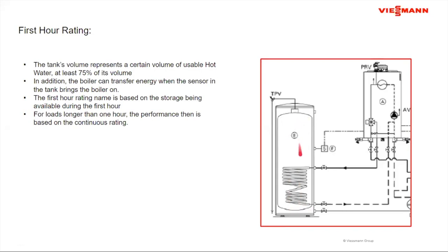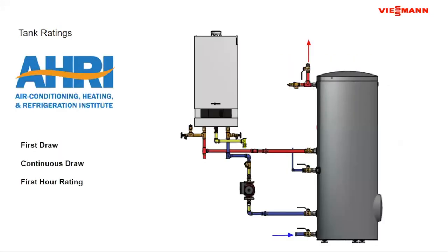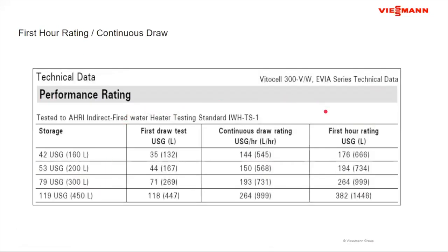But then that 75% is also supplemented by the boiler providing hot water through the coil and helping recover the cold water that's coming in, to push the performance of the tank well beyond just the volume of the tank itself. From a performance standpoint, this is generally referred to as the first hour rating because the tank's volume is available in that first hour. If I look at a 2 or 3 hour rating, I don't necessarily have that volume available, so I can't count on it. For longer performances out of the tank, we typically shift over to the continuous rating of the water heater. When I look at tank ratings by AHRI, the Air Conditioning, Heating, and Refrigeration Institute, that's where our ratings come from. You'll see that these tanks always have a first draw rating, a continuous draw rating, and a first hour rating. Three individual tests, but all three are talking about the performance of a single tank.